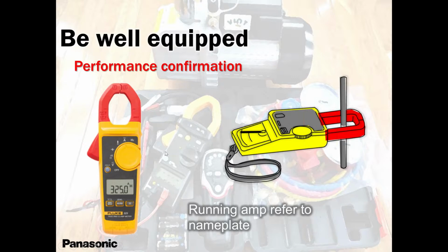Amp meter. Amp meter is good for running amps. Always good for running amps. When you're checking communication between indoor and outdoor, this amp meter might not be a good friend. I have noticed it's giving me wrong readings when I'm checking communication between number 2 wire and number 3 wire on the communication line from indoor to outdoor. Whenever I used an amp probe meter, the results of the voltage that I was expecting were not good enough. And sometimes when the voltage is not good enough, we can condemn the board, indoor or outdoor board. Meanwhile, it's our meter.